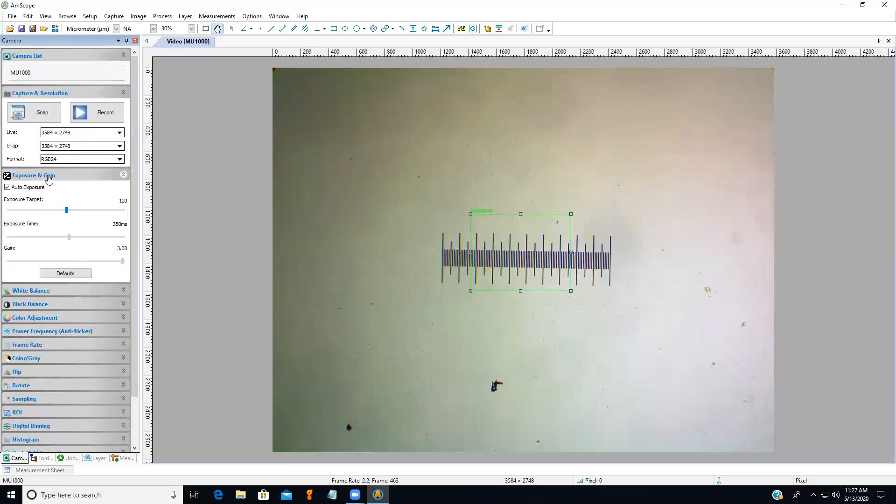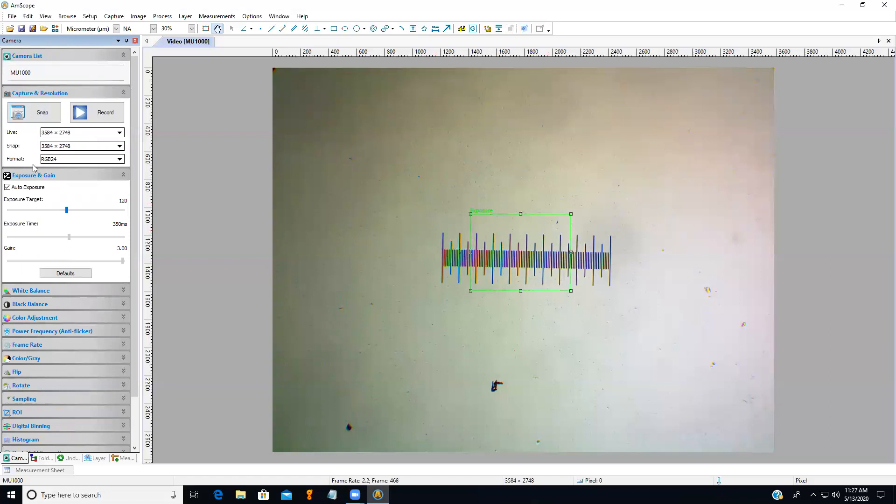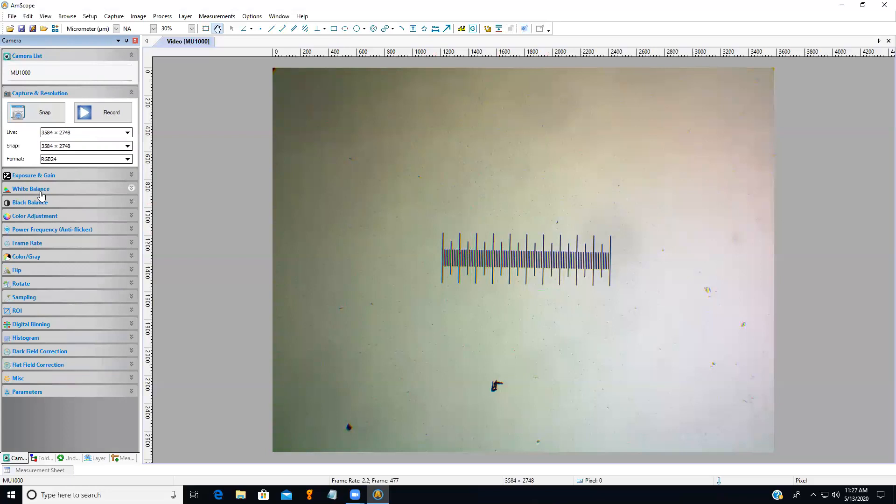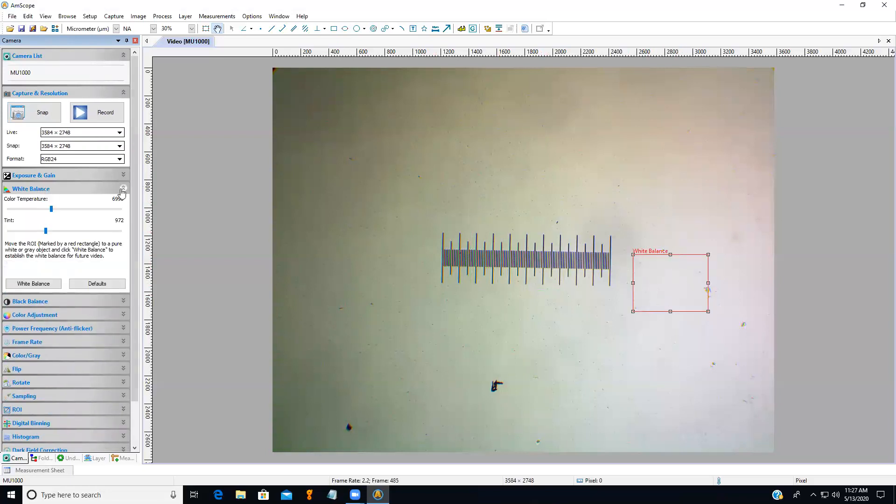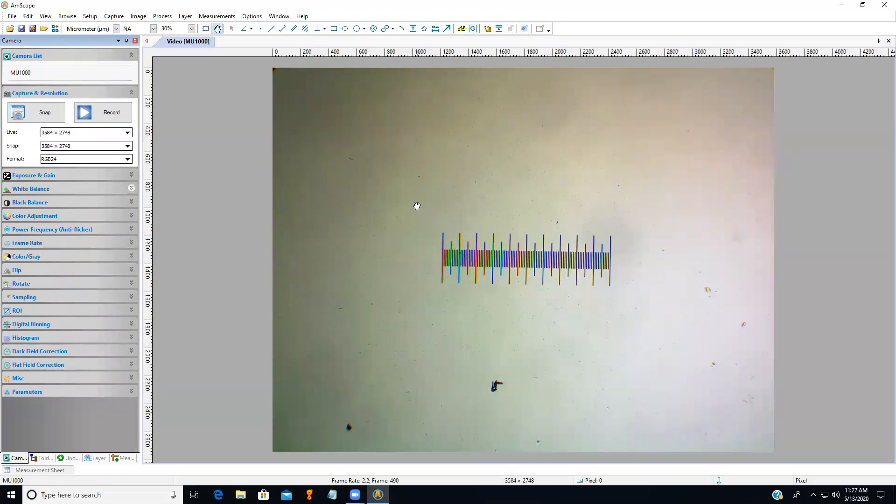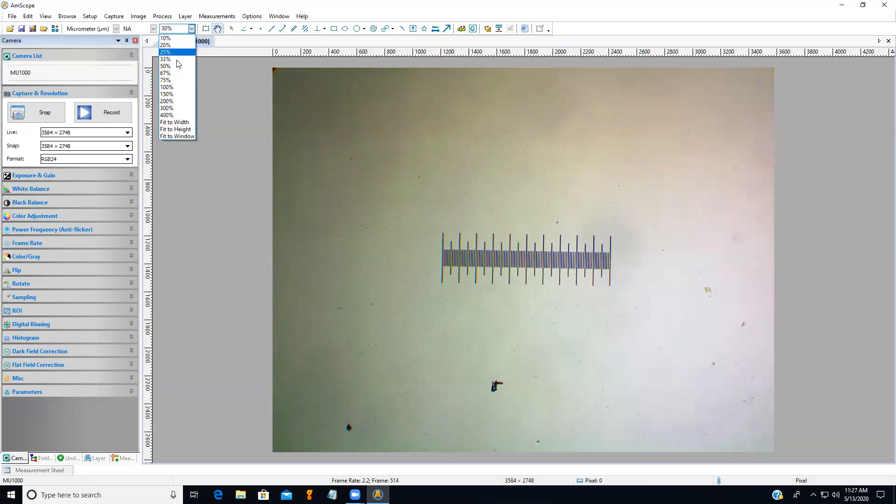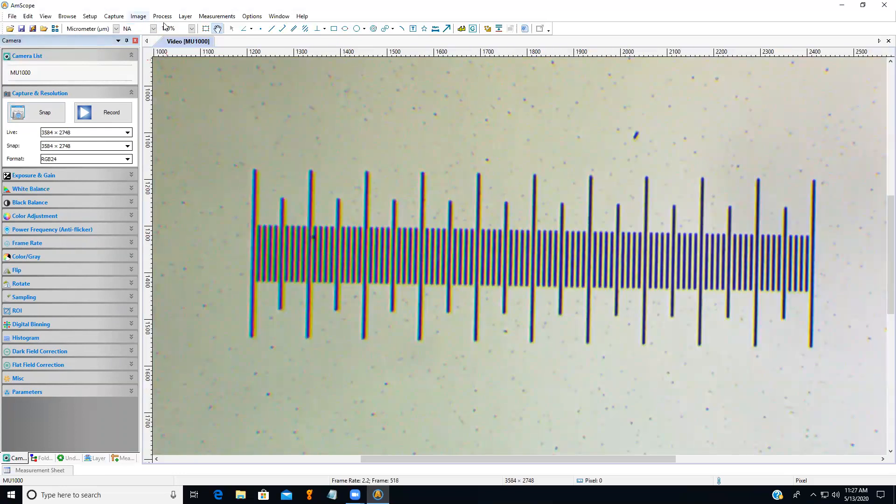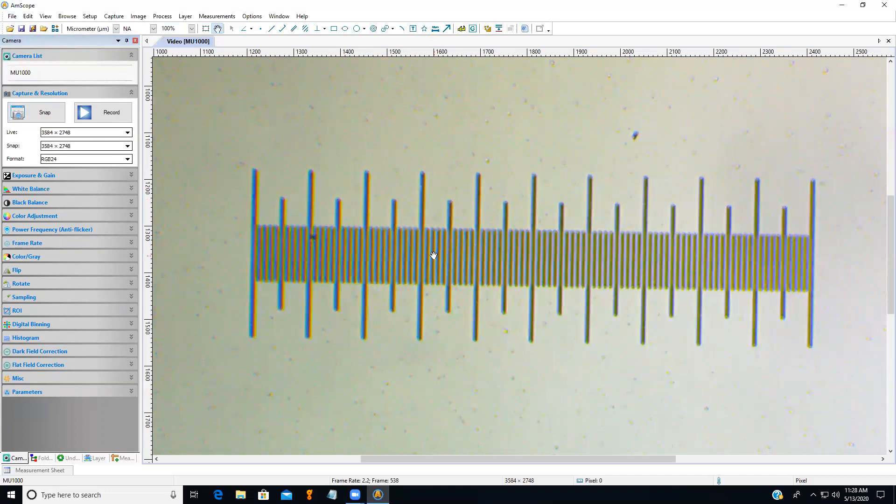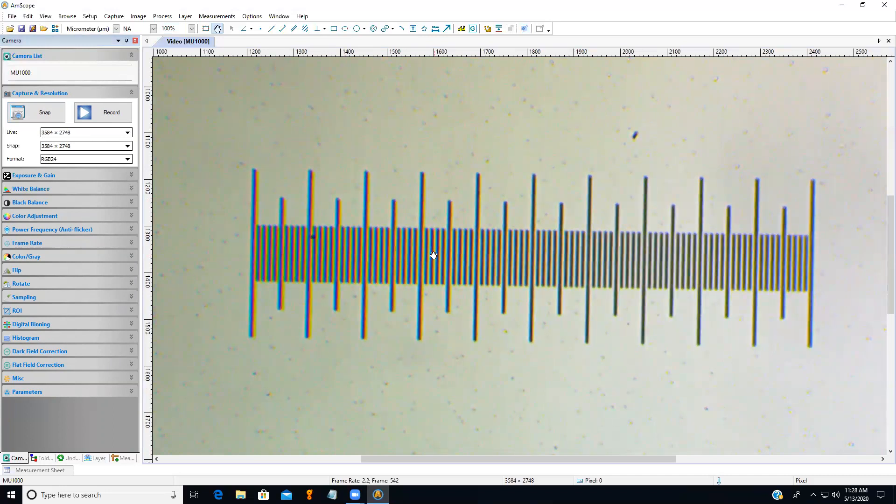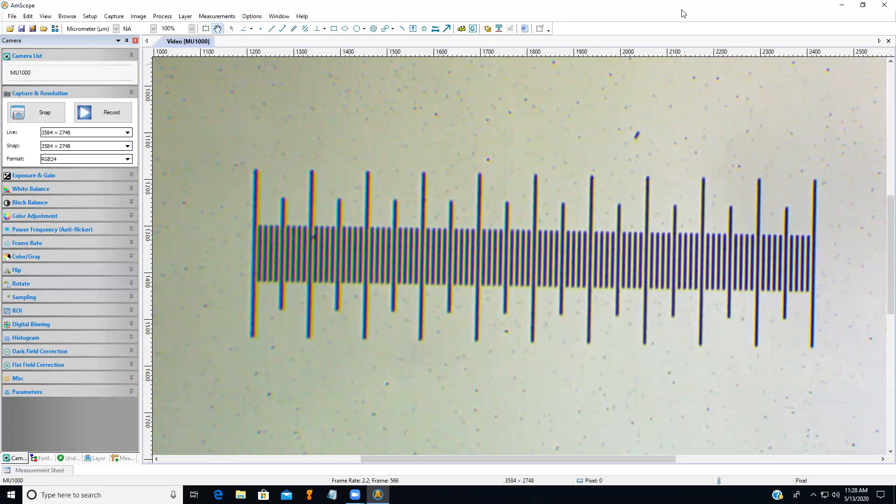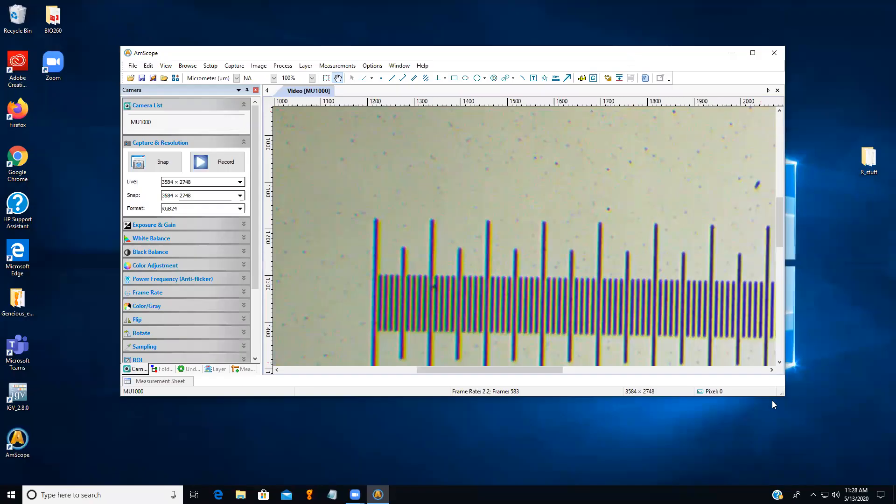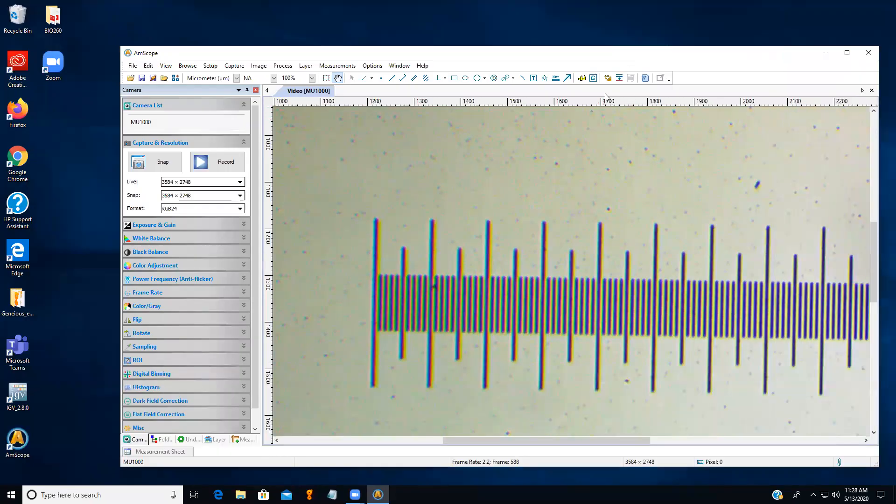A couple other things are exposure. So if it looks too dark, you might want to adjust exposure. I'll talk about that in a different tutorial. White balance, also establishing what is white. That's going to be another important part. But for now, all we care is the distances. So for calibration, you want to be at maximum resolution and you also want to be at 100% zoom. So that's up here. So I'm zoomed in all the way. If it's a little blurry, you can fine-tune it with the fine focus knob on the side of the microscope. Okay, this is pretty good. We can see all the lines on pretty well. So now next up, we're going to go to calibration. So I'm going to have to adjust the window a little bit.